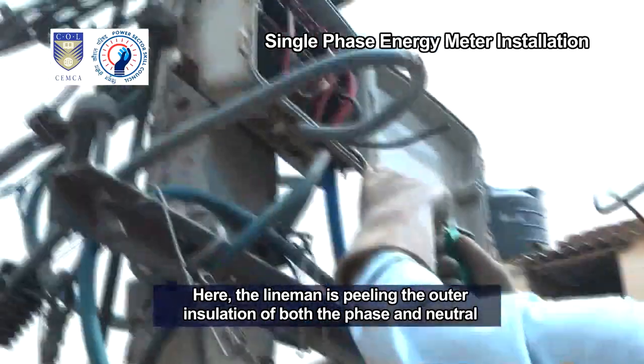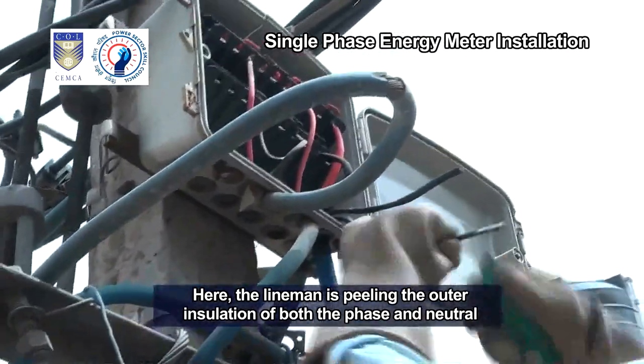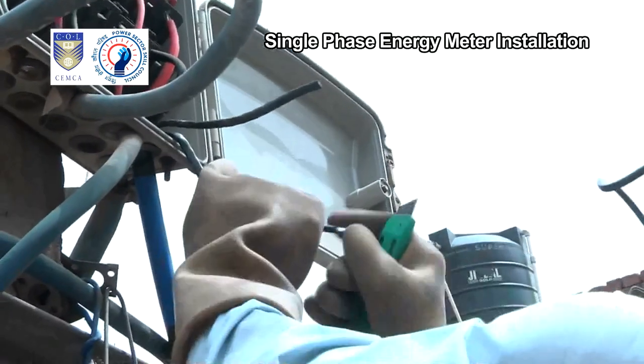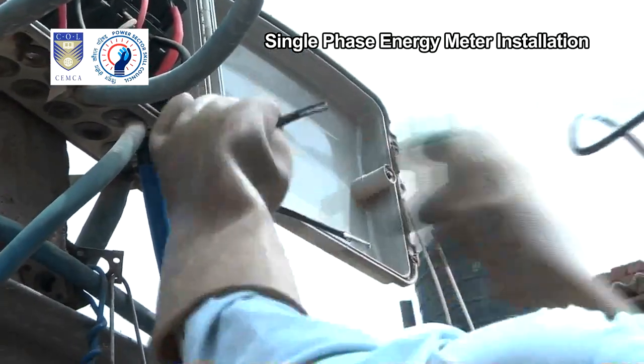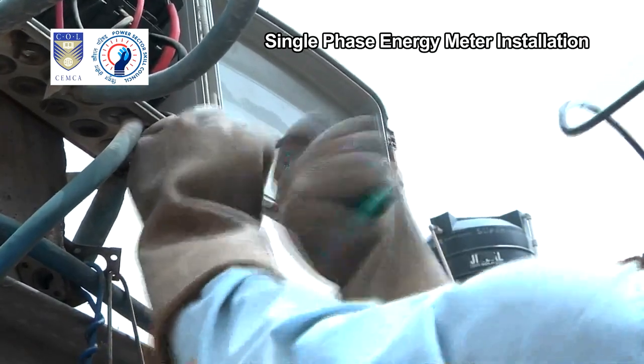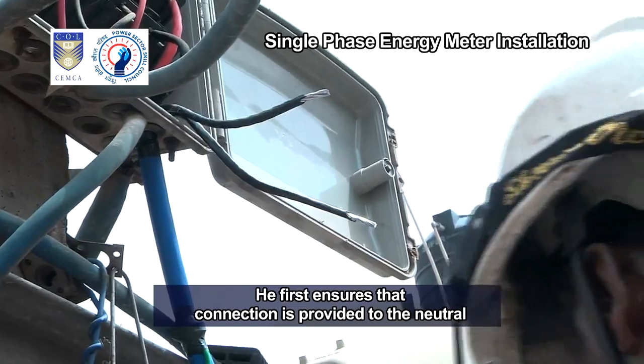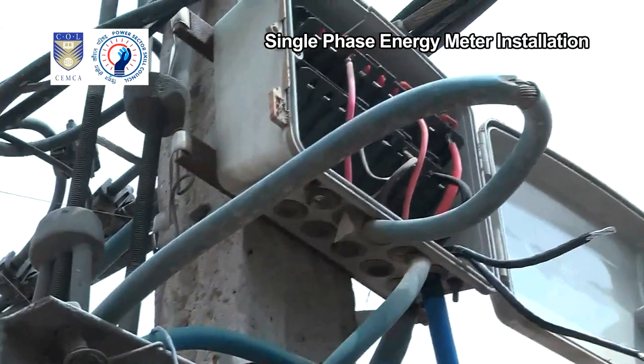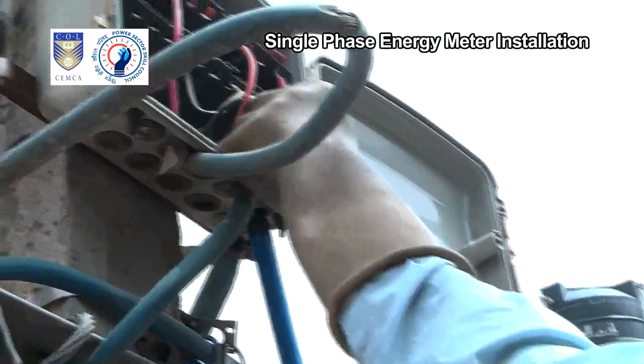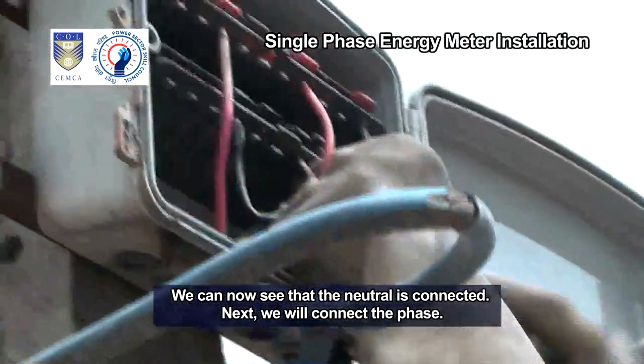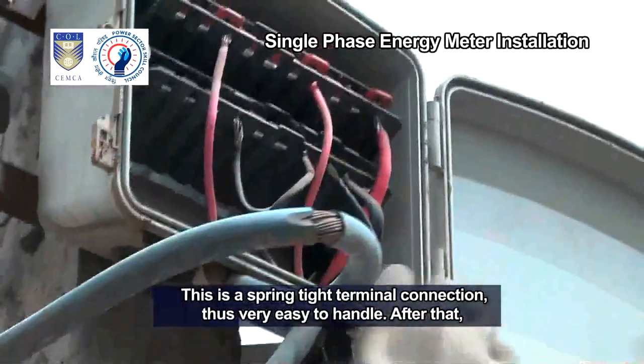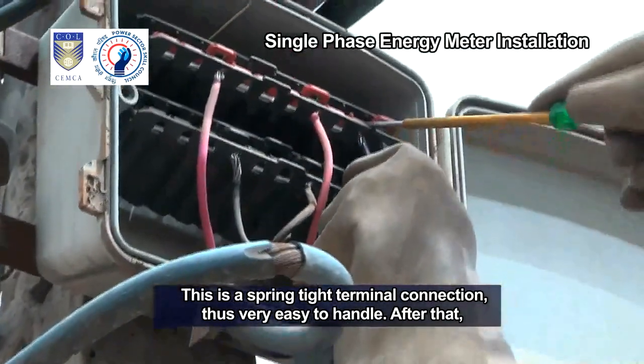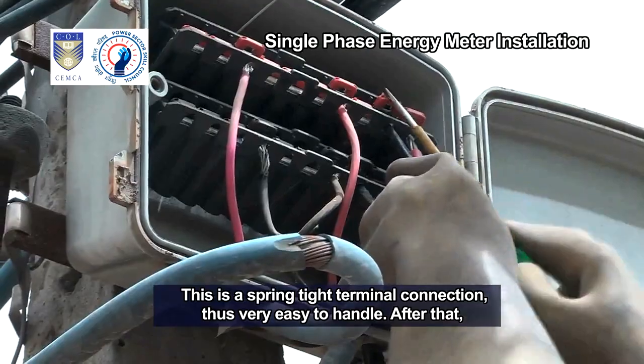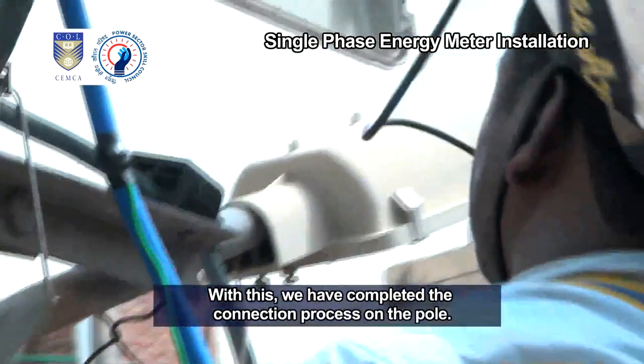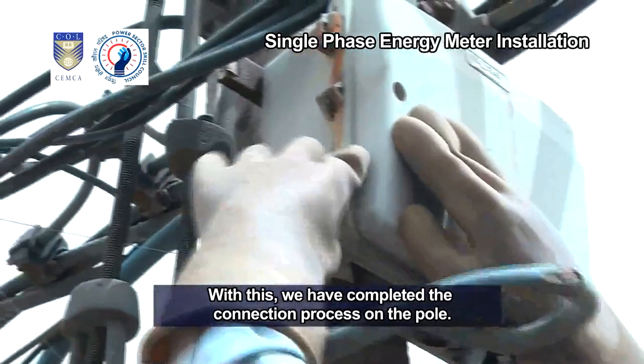Here, the lineman is peeling the outer insulation of both the phase and neutral conductor wires. He first ensures that connection is provided to the neutral. We can now see that the neutral is connected. Next, we will connect the phase. This is a spring-tight terminal connection, thus very easy to handle. After that, the distribution box is closed. With this, we have completed the connection process on the pole.